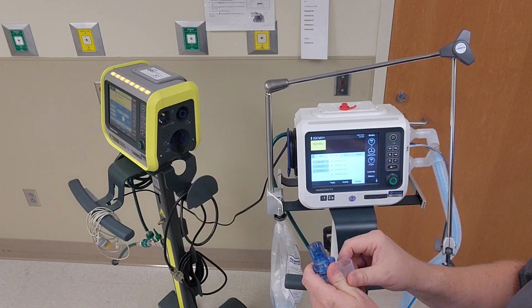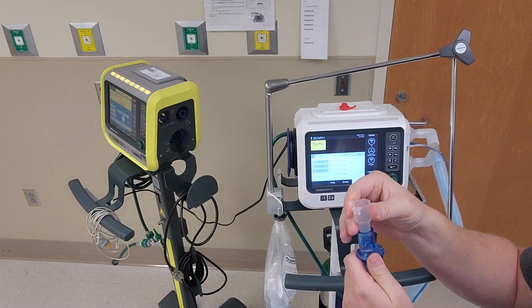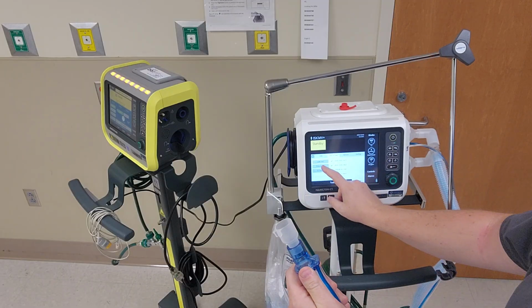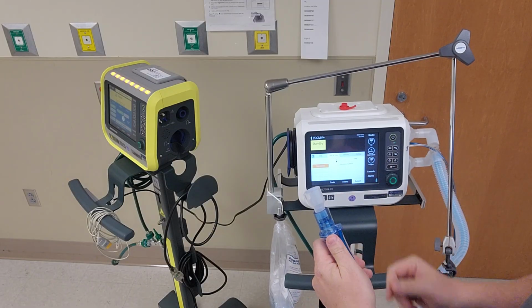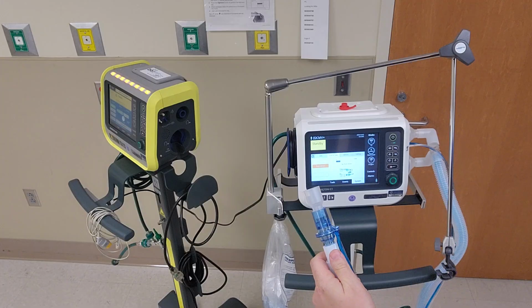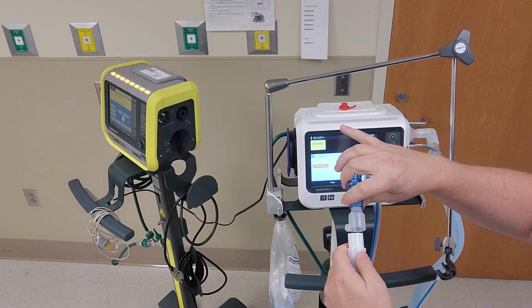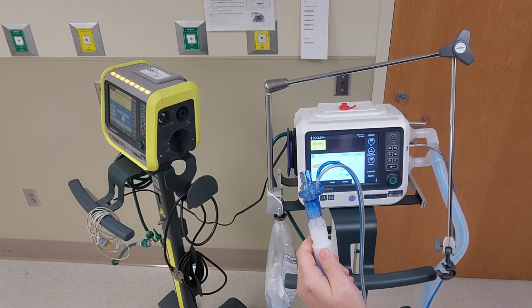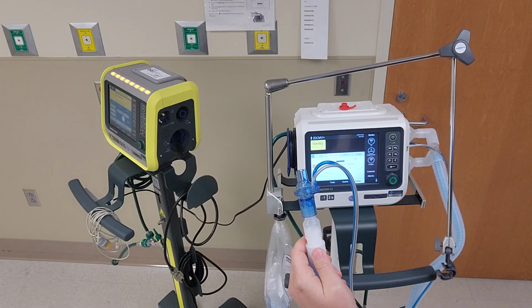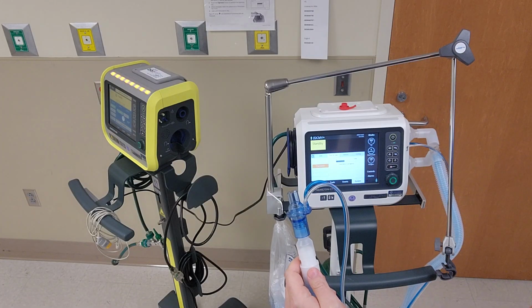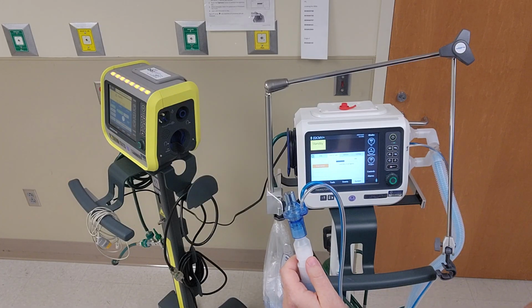Then we're going to do a flow sensor test. Take off the little clear piece, stick it on the end, hit flow sensor. It says to disconnect the patient. Now it's saying to flip it, so we're going to flip it upside down. Wait for it to tell you to do otherwise, so it's currently calibrating.